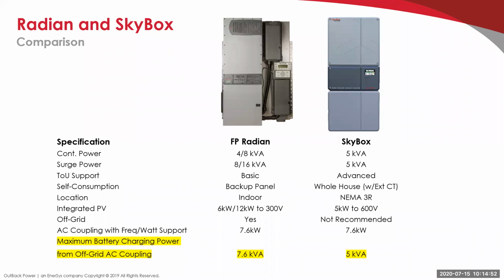Just a quick side-by-side. I mentioned that the Radian is either a 4 or an 8 kVA unit. The Skybox is a 5 kVA unit. Surge power: the Radian is officially rated at 2 times its nameplate for surge. Anecdotally, it can surge even higher than that because of the transformer it has on board, whereas the Skybox has no extra surge capability because it has no transformer on board.